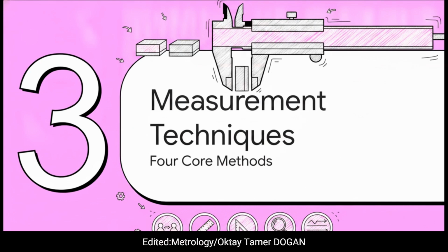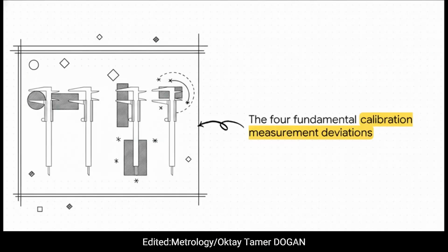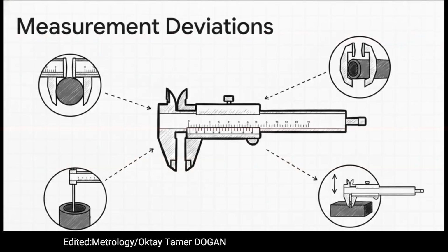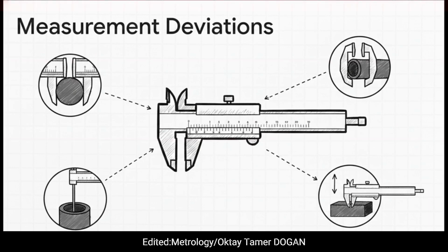Okay, Section 3. The 4 measurement techniques. This is where we get our hands dirty. This is the core execution workflow, utilizing the direct comparison method for calipers up to 2,000 millimeters. This diagram essentially maps the whole testing landscape. We are actively forcing the caliper to prove its precision against flawless parallel gauge blocks across every single measuring face it has. Depending on how the caliper is physically built, a technician has to hunt down up to 4 specific measurement deviations: outside diameter, inside diameter, depth measurement, and step measurement deviation. You have to interrogate every functional surface.